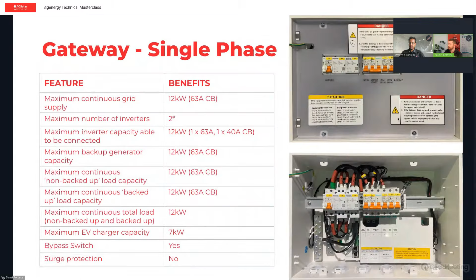Now, the single phase gateways don't come with surge protection inbuilt, but there is enough room in the switchboard to easily add that. Now, looking at the three-phase gateway, it's essentially the exact same setup when it comes to bypass switch, inverter inputs, very similar arrangement, but more beefed up, and a lot of it's 4-pole because we have generator inputs in both the single phase and three-phase options.